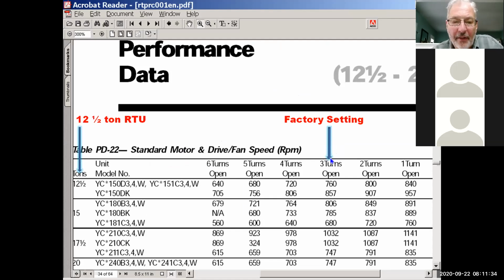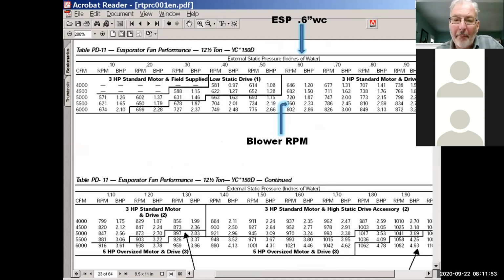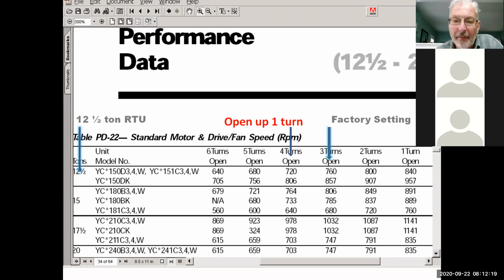The factory sends all of our belt drive units set with the pulley open 3 turns. Okay, so on this 12.5-ton unit, 3 turns open means I've got 760 RPM. So if I look at my blower curve at a 0.6 static at 760 RPM, I'm moving 5,500 CFM of air. Actually, I'm moving too much air for that unit. Unless you're out west or in an area where you don't have to worry about sensible cooling or latent cooling, you're at 450 CFM per ton or 440 per ton, which is a little bit high for our market here.